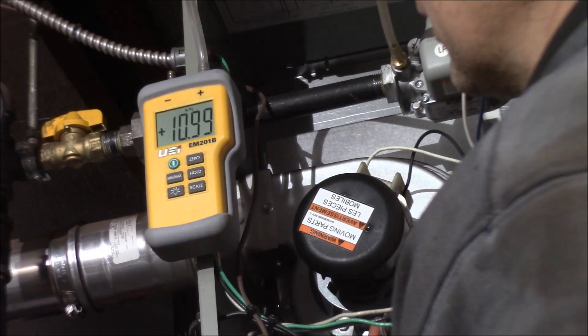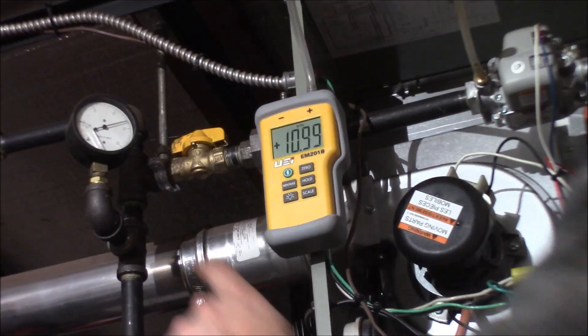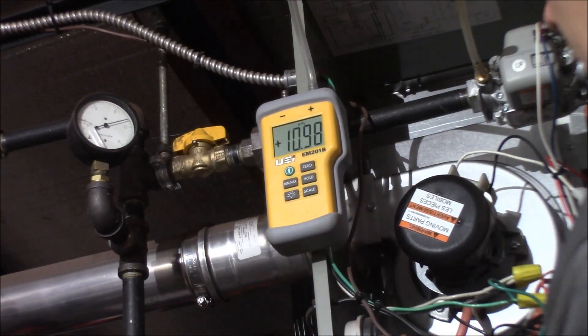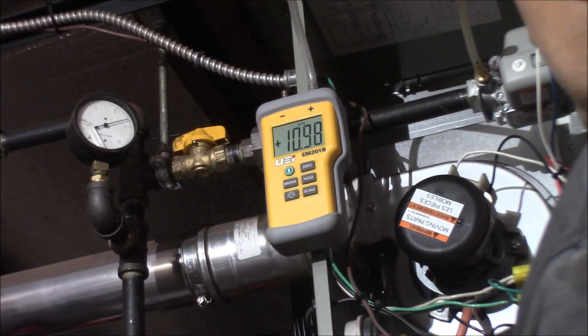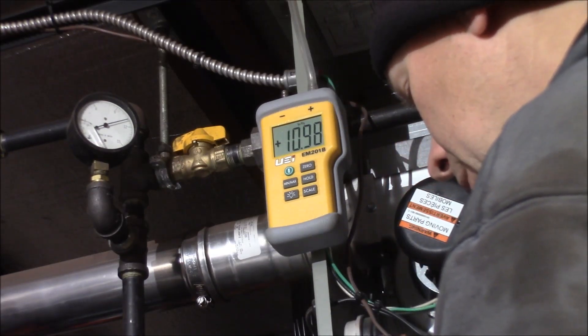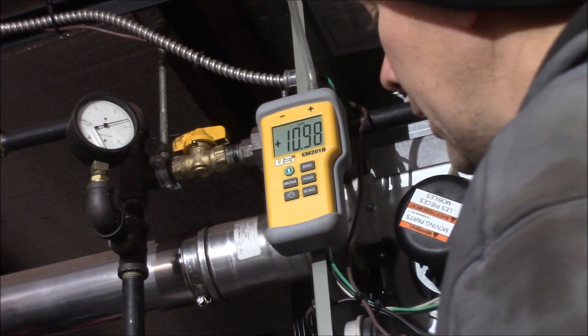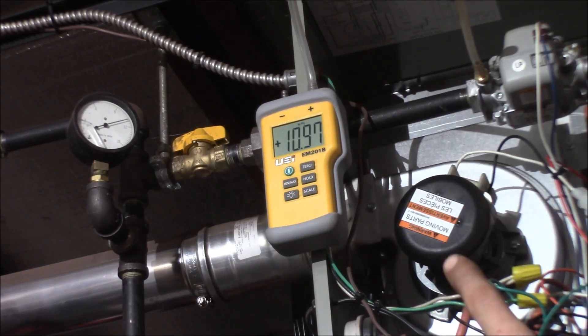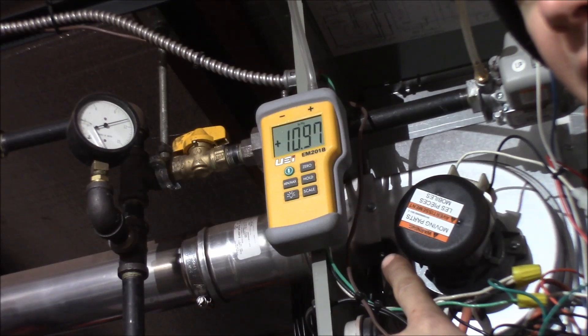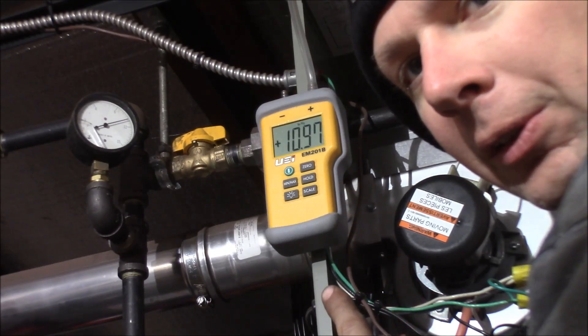So right now we're showing 11. So our gauge is right at 11, and this is right at 11. So what I want... It said inlet pressure minimum 12. So I've got 11 right now. It said they want 12. I'm going to fire up the heater and see what it drops to.